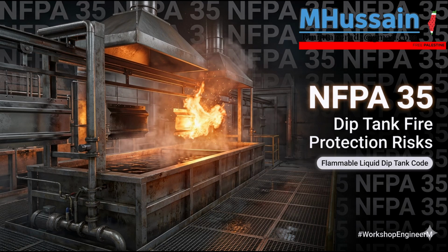We then built the physical box, enforcing the absolute ban on subterranean basements to prevent heavy vapor pooling, fortifying load-bearing steel columns with expanding intumescent char coatings, and engineering a massive, energy-intensive mechanical ventilation system designed to meticulously sweep explosive vapors right off the factory floor. We relieved the pressure of inevitable explosions with sheer blowout panels, and we held back the invisible vapor monsters using positive pressure clean rooms for our electrical gear. We plumbed the mechanical heart of the facility, completely outlawing brittle, shatter-prone cast iron in favor of highly ductile steel. We enforced fail-closed pneumatic valves that default to safety when the power dies, and we eliminated the oxygen from pressurized pipe transfers using inert nitrogen gas blankets.